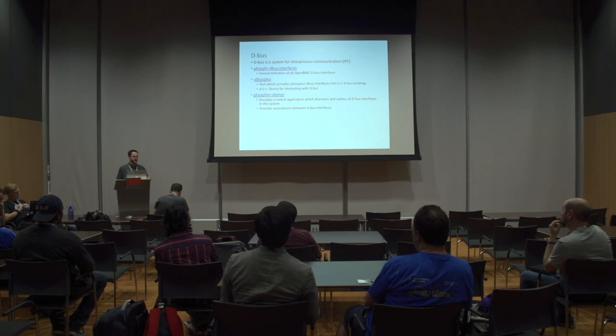So, if you've got an error log for a thermal event, you can associate that error log with the thermal sensor on the dbus bus that caused that error log. So it's a different way to do things like that. The error log could also be associated with the inventory device that is causing the error, right? So "replace this fan" would be the association you get with the object manager between an error log and a physical device.